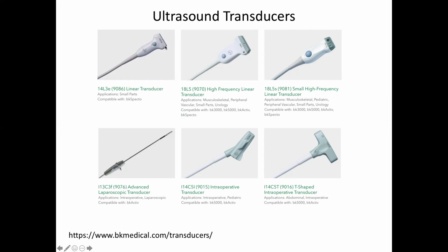Normally just use a linear array like this and you tilt it to get the thing. You can get something that's more like a square as opposed to a linear array, so a square. And this is one where using the elements on the transducer, you can rotate the scan plane or make it go back and forth just by changing the phase of the ultrasound on the transducer.